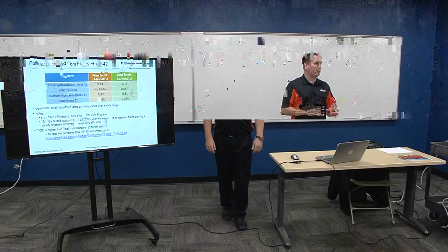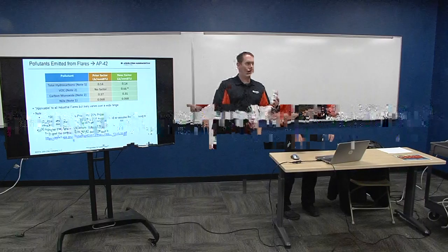And that's because it assumes 98% or greater than 98% destruction efficiency. But there's a caveat in there that your flare has to be properly operated. So now with the new regulations, people have to track and prove. Because one thing I didn't cover with these new regulations, companies have to take snapshots every 15 minutes of their operation to prove that they're staying within these bounds.